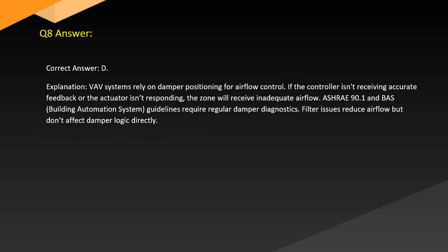Answer. Correct answer: D. Explanation. VAV systems rely on damper positioning for airflow control. If the controller isn't receiving accurate feedback or the actuator isn't responding, the zone will receive inadequate airflow. ASHRAE 90.1 and BAS (Building Automation System) guidelines require regular damper diagnostics. Filter issues reduce airflow but don't affect damper logic directly.